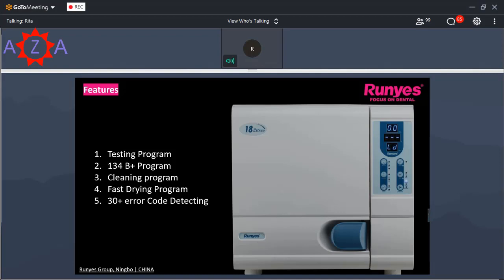And the next one, the cleaning cycle. This is a special program for RUNYES autoclaves only. For our autoclave, every 100 cycles the machine will automatically remind you to run this cycle to clean the steam generator, valves, and pipes to protect the machine. It will take 30 minutes: 20 minutes of cleaning and the last 10 minutes of drying. So this is also an important program.